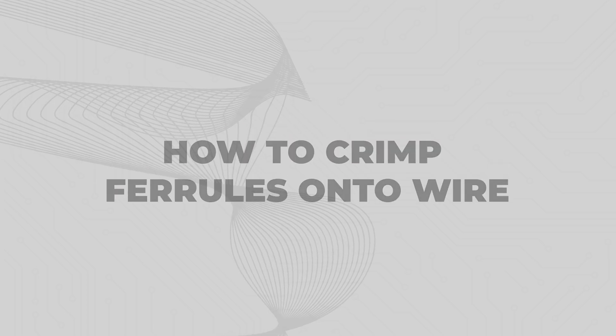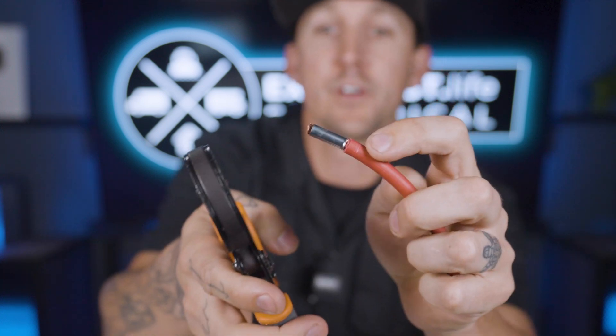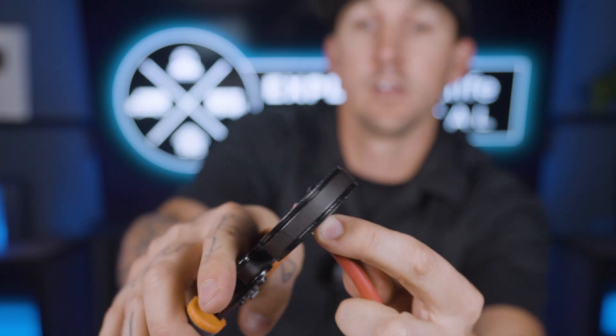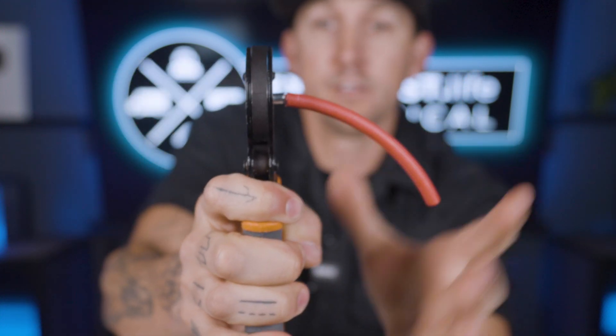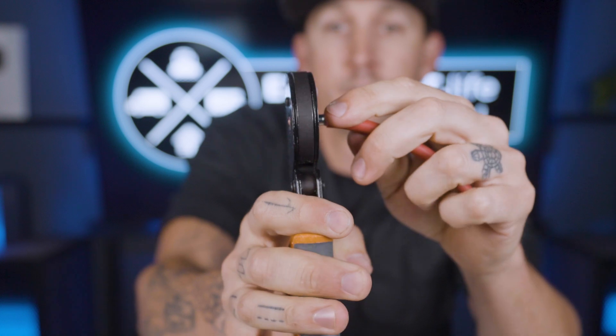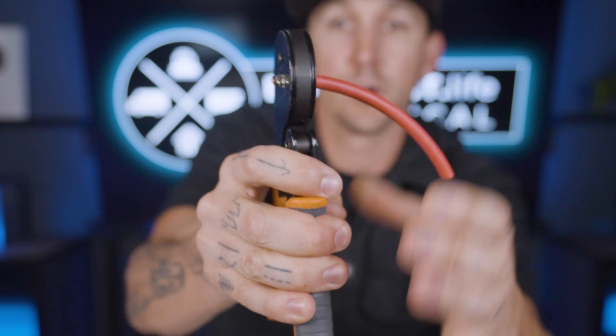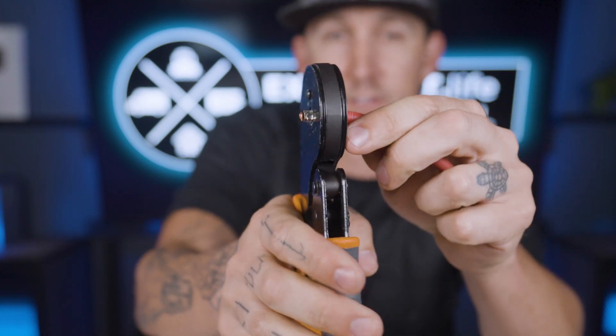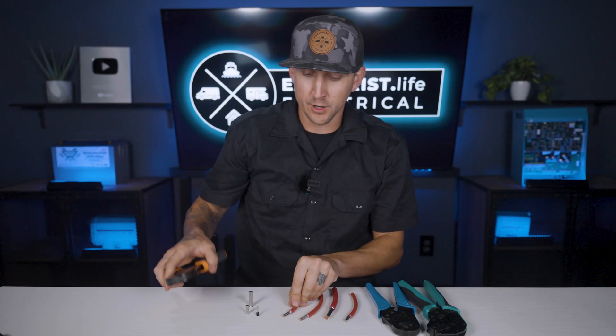How to crimp ferrules onto wire: to actually crimp a ferrule onto a wire, you simply put the ferrule onto the stripped wire, put the ferrule into the ferrule crimper until it's barely through the end, and then squeeze the ferrule crimper handles. You may have to do it twice if the first crimp doesn't go all the way to the end — just readjust the crimpers and give it another squeeze. This process of crimping a ferrule is going to be the same regardless of what size of wire or crimper that you're using.